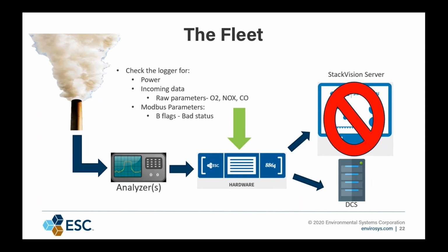If you know that your data logger is supposed to be receiving all or some values via Modbus and you see B flags on parameters, it's very possible that you could have a Modbus issue on your hands. Unfortunately, troubleshooting Modbus is something that we won't be covering in this course, but we do have a ton of troubleshooting Modbus webinars that are already available on our website. So after this, if you still have questions on Modbus, please feel free to go to the website and take a look at those webinars. They are very informational.